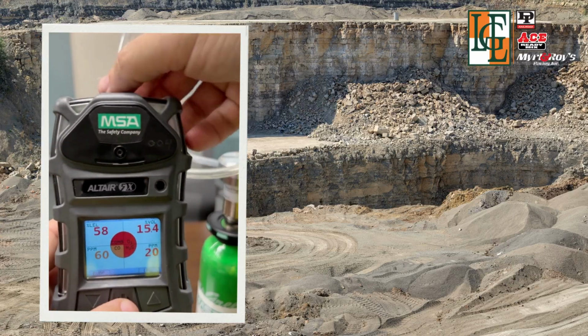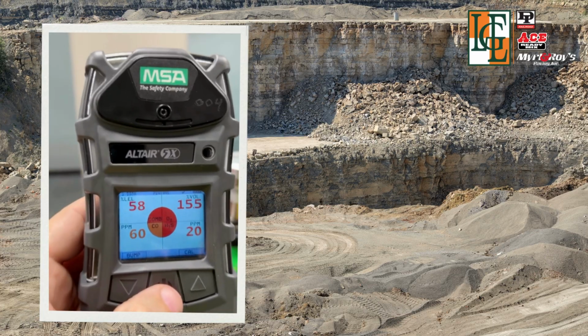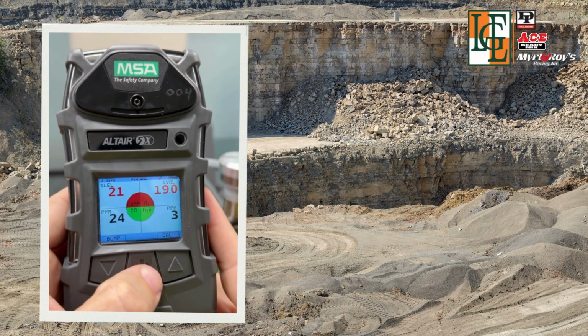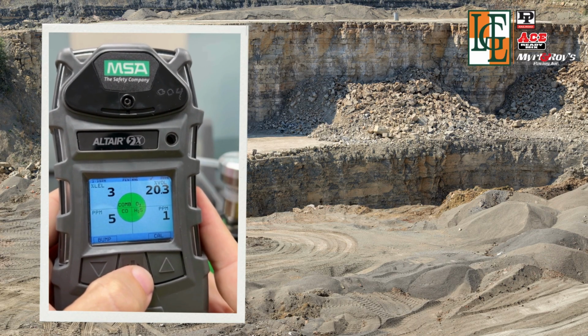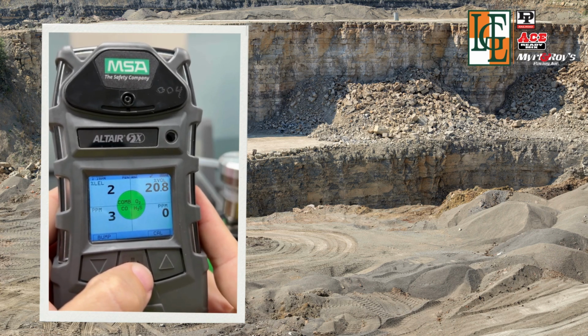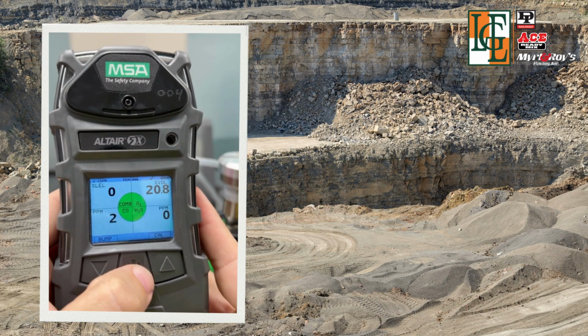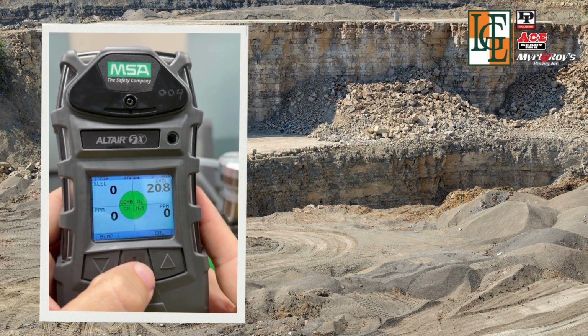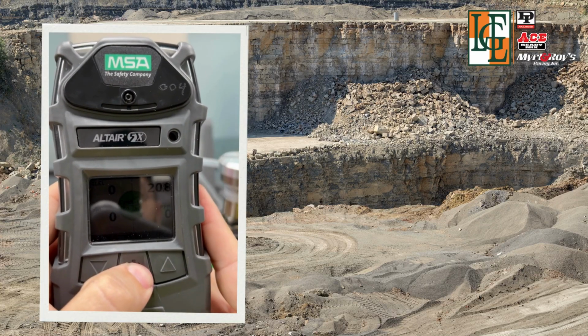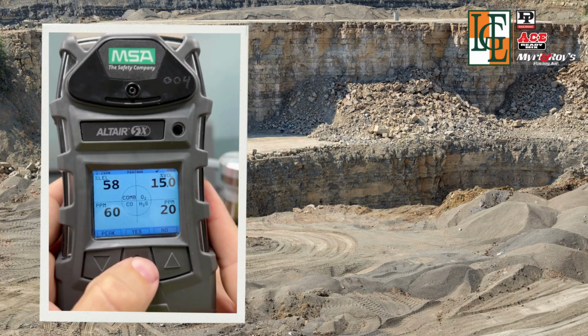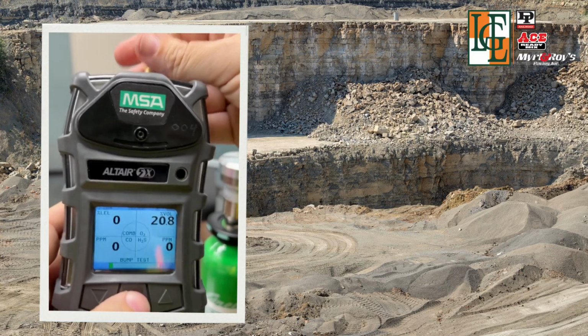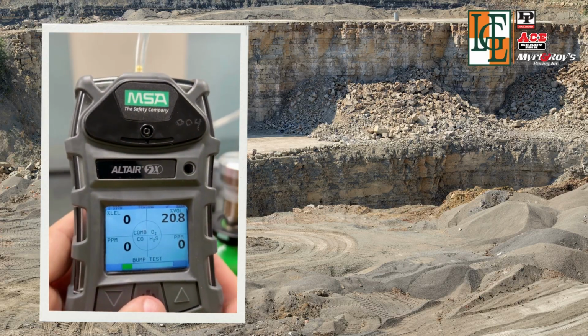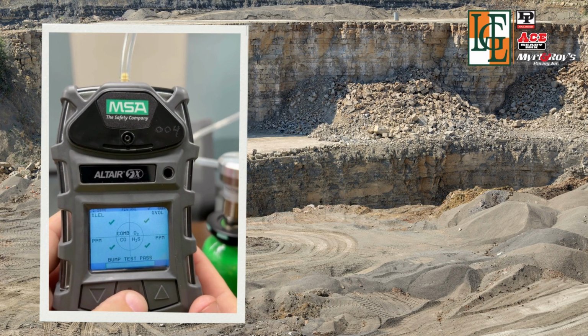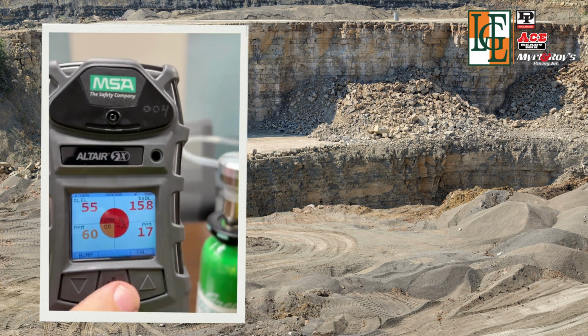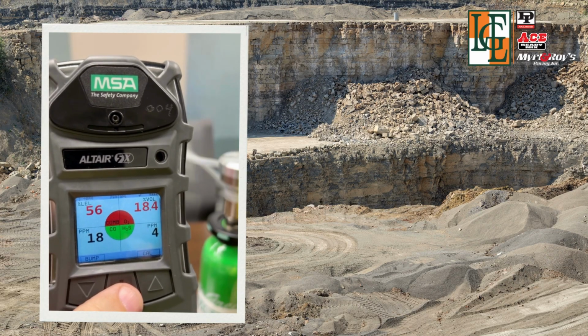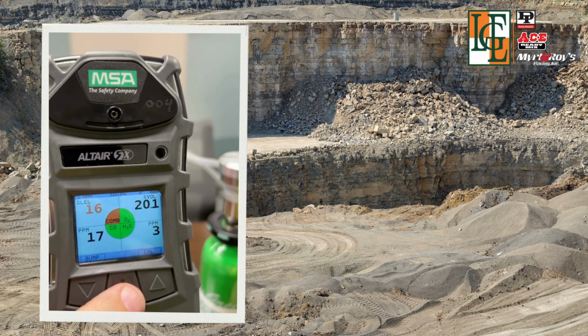It'll be all right. So let's disconnect, and we'll make sure that these values go back to 0. Should bring us back to 20.4 or 20.8 for oxygen, and everything else should be reading zeros. All right. Now that we've got it calibrated, let's do a bump test. All right. Bump test passed. Watch these values go back down to 0 again, and our oxygen should go back to 20.4 or 20.8, somewhere within there.